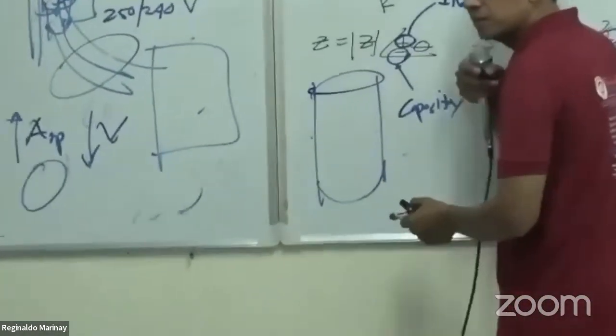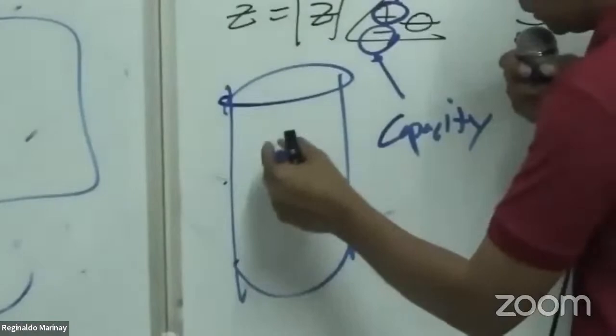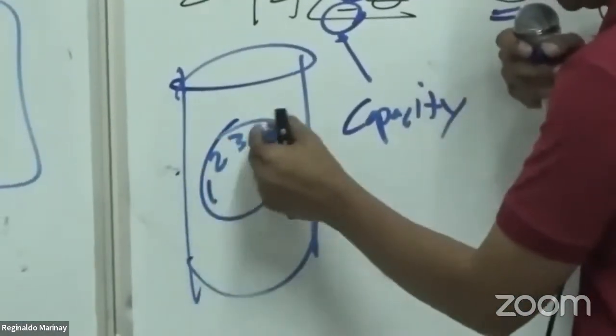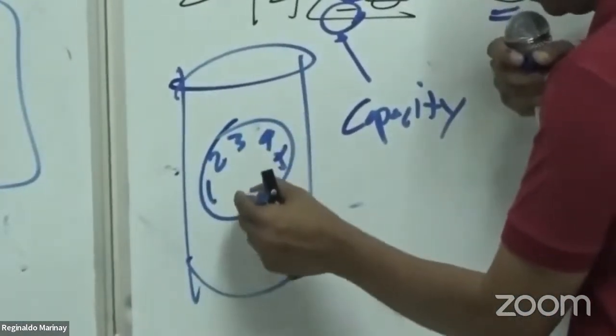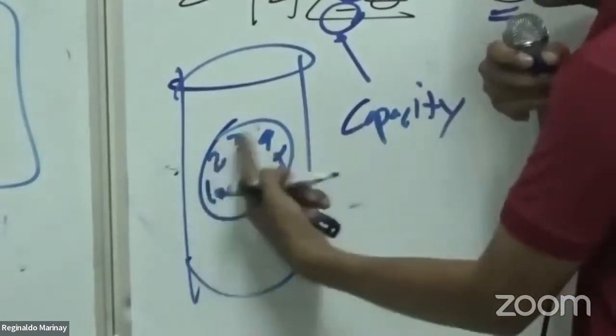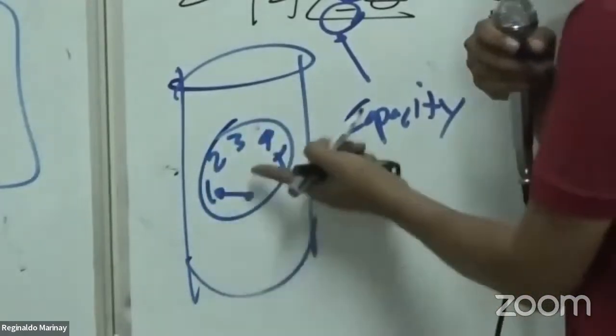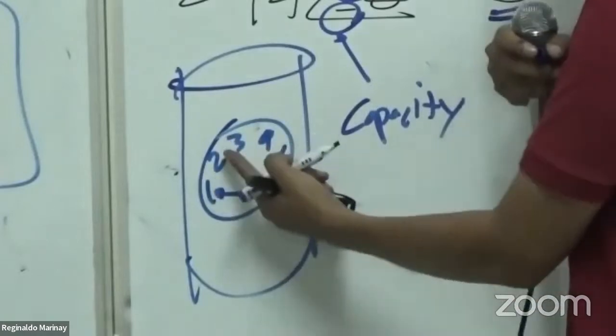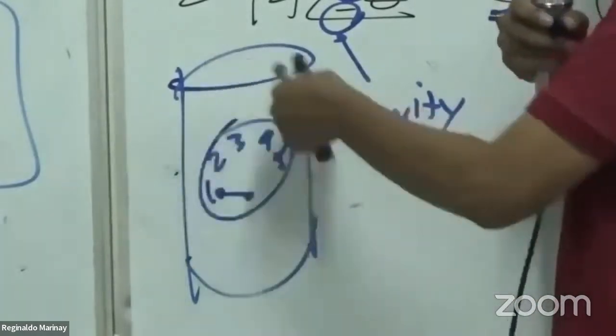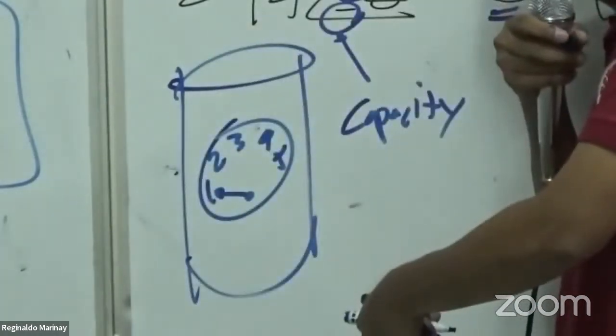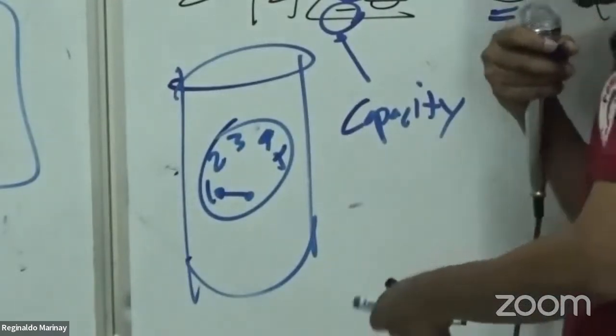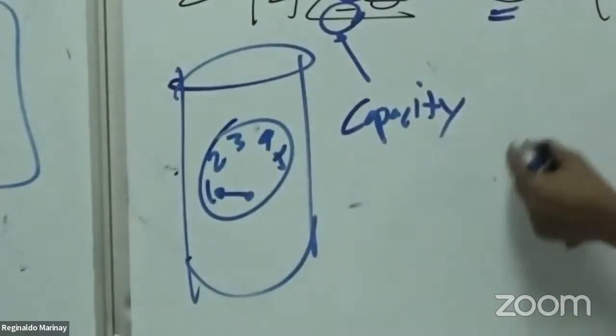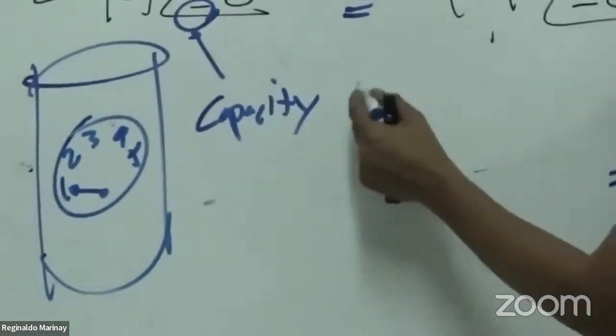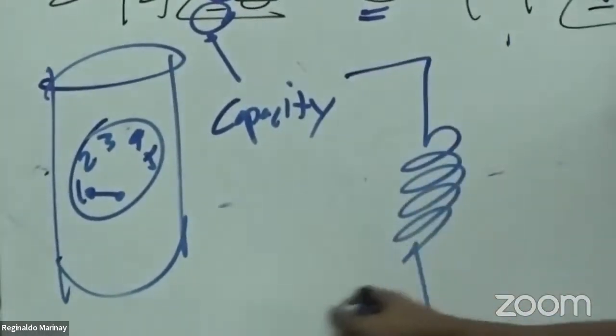It's like a watch with one hand, without a minute hand. You see this one? There is 1, 2, 3, 4, 5, and then there is an arrow here. If you increase the number from 1 to 2 to 3 to 4 to 5, that will also increase the output voltage. That's the principle of the tap changing transformer.